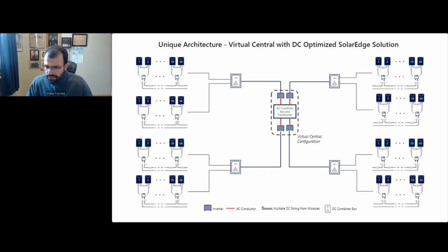It combines the benefits of virtual central inverter configuration, which are low AC costs and losses, and easier O&M, with the benefits of string inverters, modularity, and plant availability. At the same time, DC cabling costs are kept low by using DC combiner box or trunk bus solutions and aluminum feeders. Superior energy production is achieved with DC optimization, which performs module level MPPT. And this is why we call this a unique architecture. That's why Varsha mentioned that that's a unique architecture, because it combines the best of both worlds.